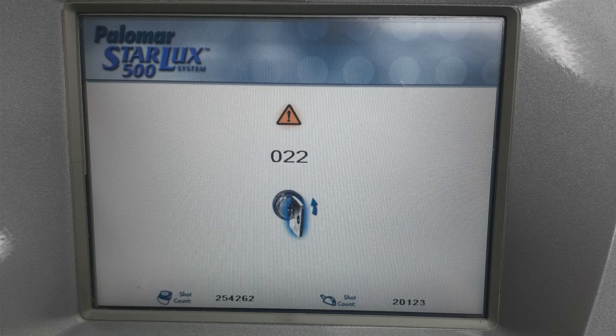At least once a day we get a phone call in our service department, or an email or call to me, about water flow errors in systems. These are typical with open devices such as Palomar, Alma, Candela, and so many others. I'll show a picture here in a moment of a Palomar Error 22, which is a water flow error on a Palomar 500, but you can see this on just about any Palomar IPL system.